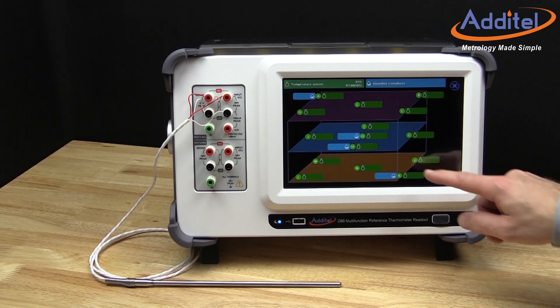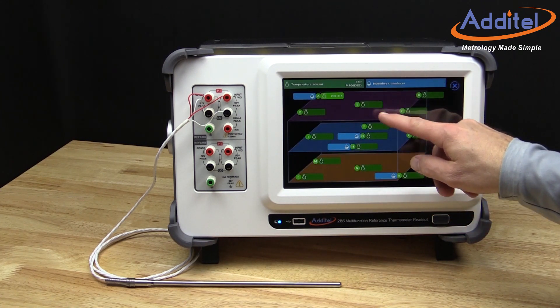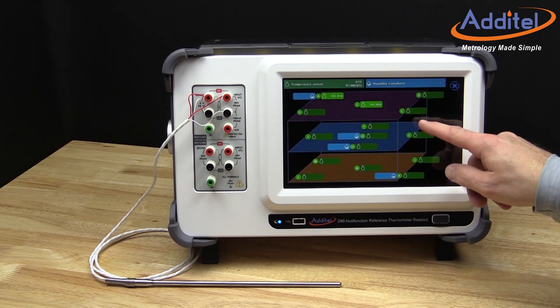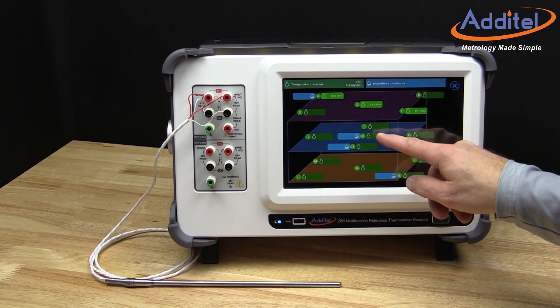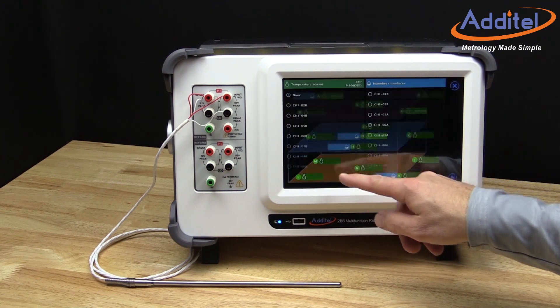Additel's unique onboard application menu provides a number of established applications to help facilitate common calibration and data collection needs. Onboard applications help guide operators through the process of mapping chambers, calibrating probes, and performance testing of heat sources, to name a few. Additel will continue adding applications as new uses for the ADT286 are discovered and needed.